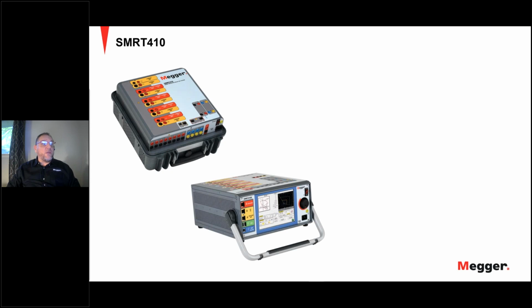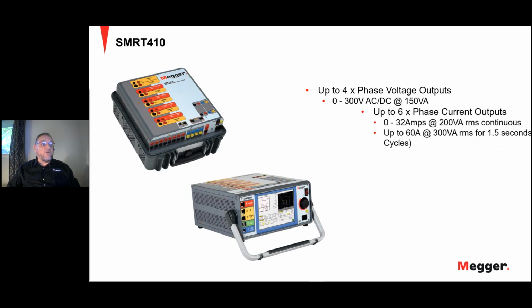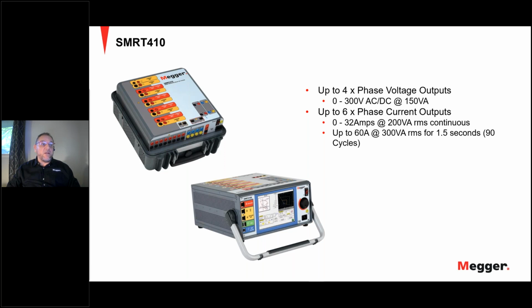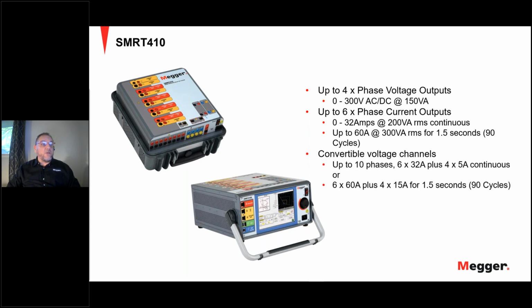The SMRT 410 is the top of the range. You get up to 4 phase voltages, 0 to 300 volt AC or DC at 150 VA, up to 6 phase currents with the same rating of 32 amps at 200 VA or 60 amps at 300 VA for 1.5 seconds. And obviously you can convert the channels as well to give you up to 10 phase currents at 6 by 32 amps and 4 by 5 amps continuous. So this makes these units very flexible and able to cover almost any application that is needed out there in the relay testing world.